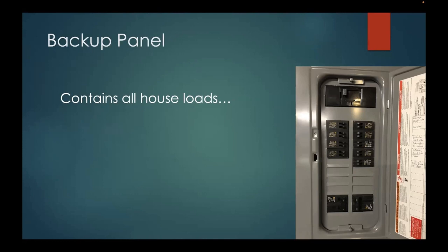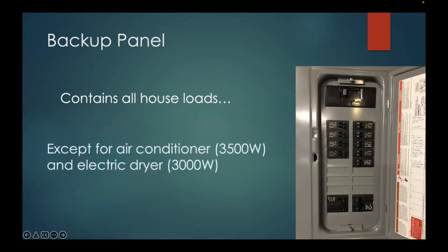My backup panel does contain all the circuits in my house. Here is my battery breaker that feeds this panel, and here is the solar breaker. The only two exceptions I left on the main panel are my air conditioner, which takes 3,500 watts, and my electric dryer, which is 3,000 watts. Everything else in my house is on this sub panel.